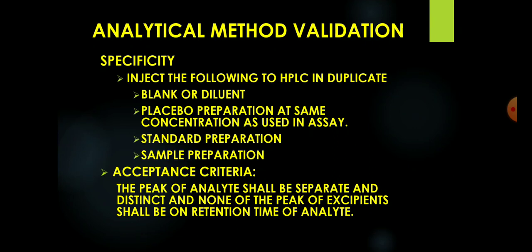The acceptance criteria for specificity is that the peak of analyte shall be separate and distinct, and none of the peaks of excipient shall be at the retention time of the analyte. If we have a retention time of 3.5 minutes for the analyte, then near 3.5 minutes we should not have any other peak.